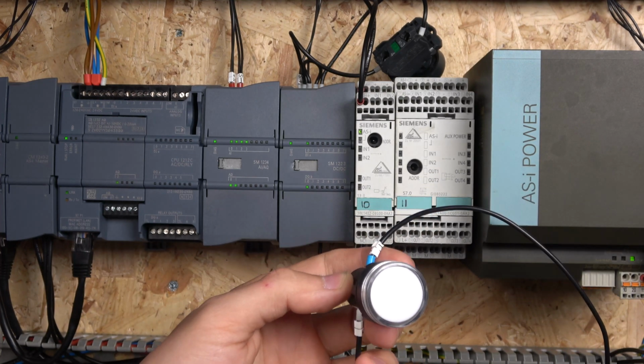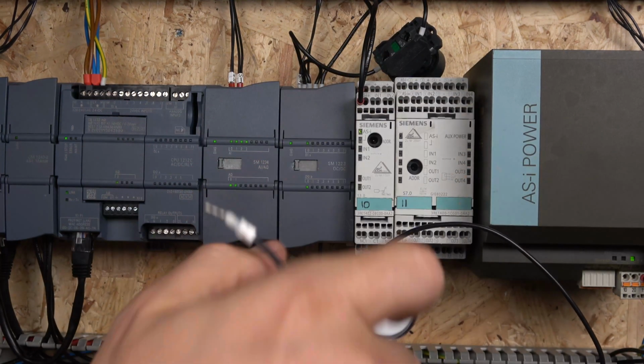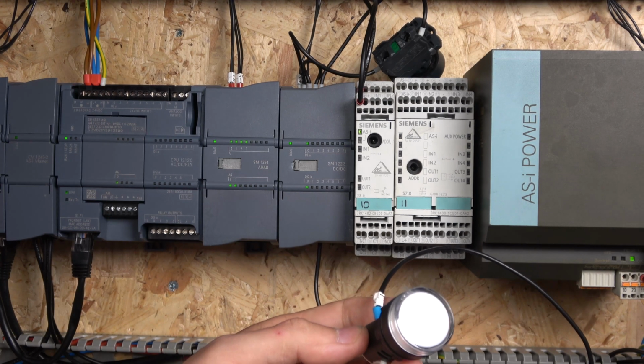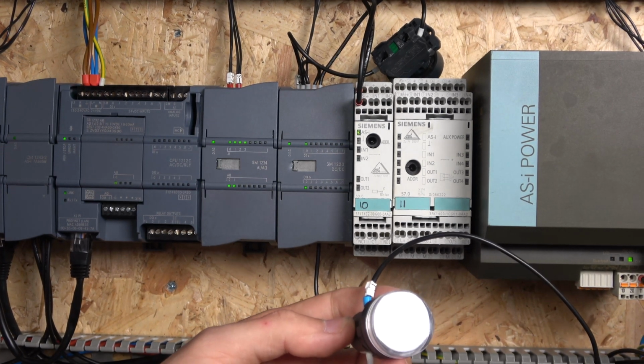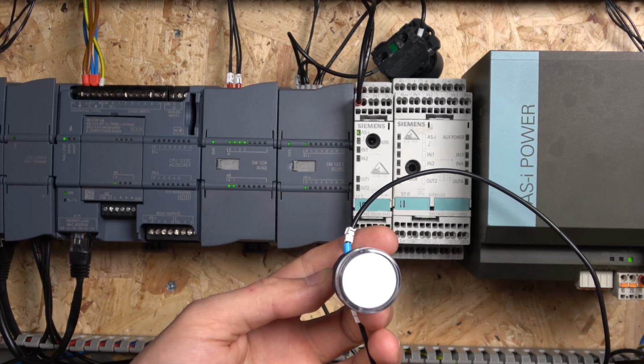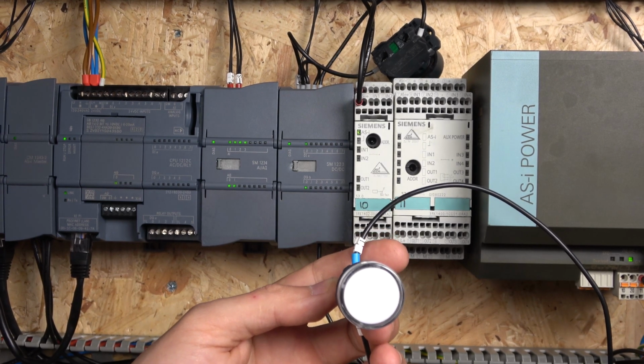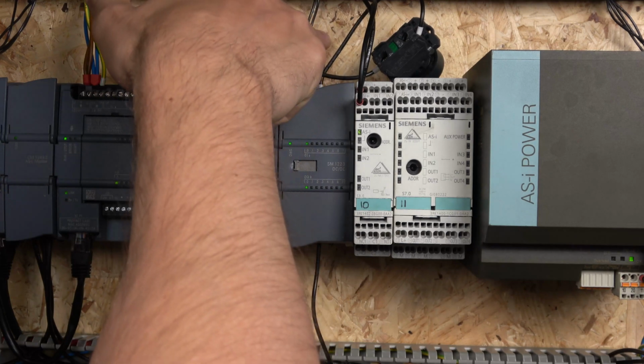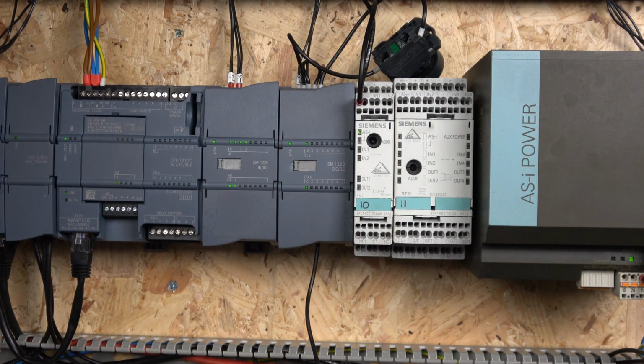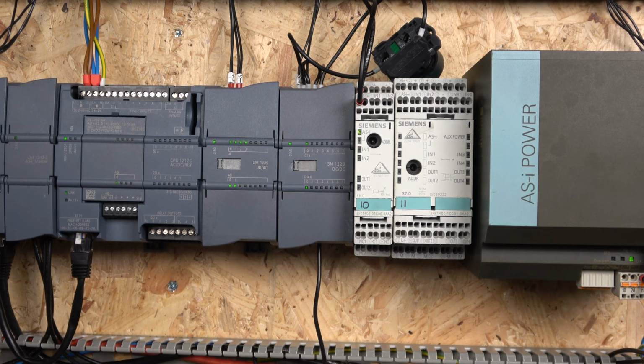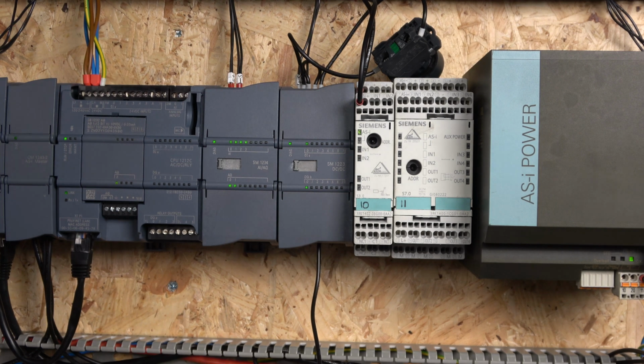What I'm going to do is take another power supply, literally there. I can't show you which one that is, and I'll attach it to the minus, and as you can see, nothing is really happening. I'm literally putting a negative in there. Nothing's happening because the negative is coming from this card's power supply in here. And that, ladies and gentlemen, is how you wire the transistor card for an S7-1200 series PLC, which is an additional card. That's what we're doing. So yeah, that will cover it.